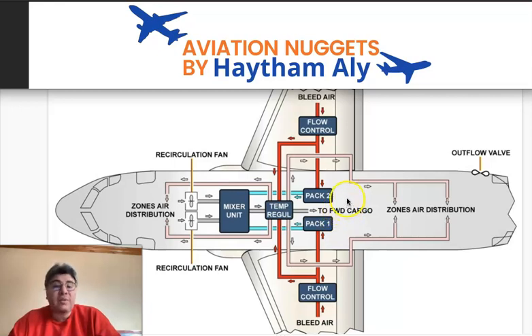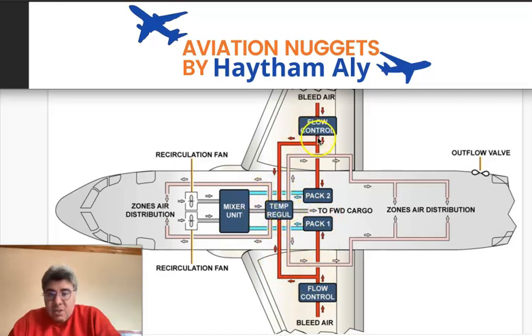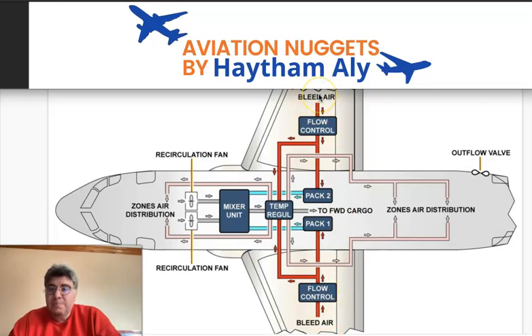We also have an enhanced or optimized temperature regulation in addition to the basic regulation done by the packs. This optimized temperature regulation depends on hot air taken from before the packs, which is added at a downstream temperature regulation point to fine-tune zone temperatures.